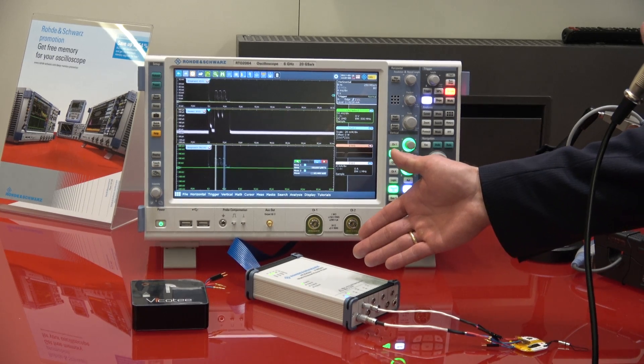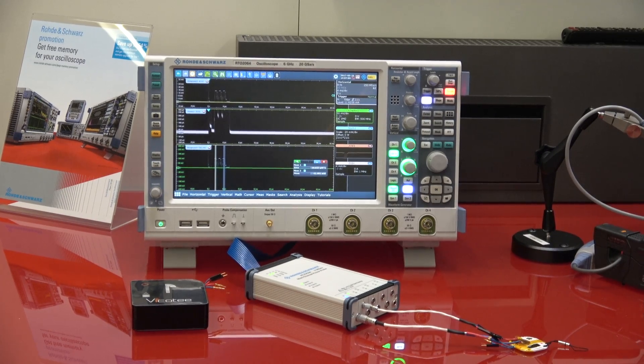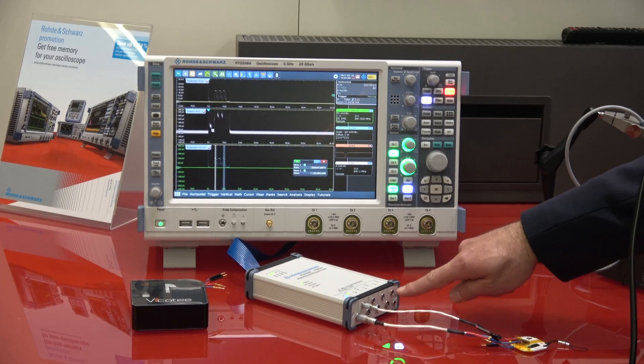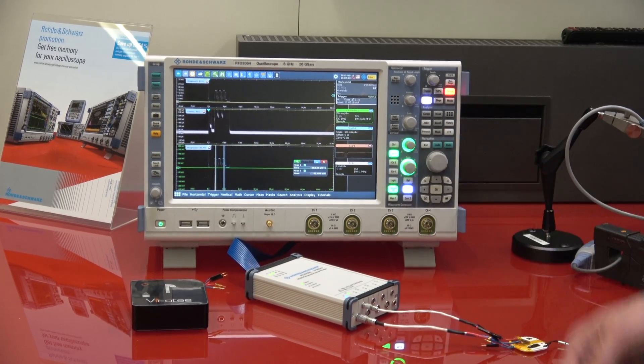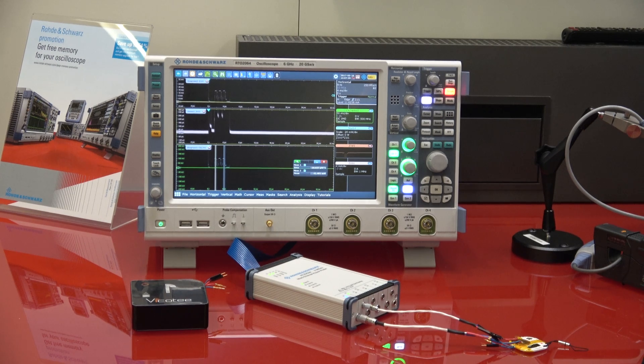This is the RT-ZVC02 or ZVC04 multichannel power probe. It features four current channels and four voltage channels, and it has an integrated 18-bit AD converter for each channel, offering that dynamic range in addition to several measurement ranges to cover the high dynamic needed for current measurements.